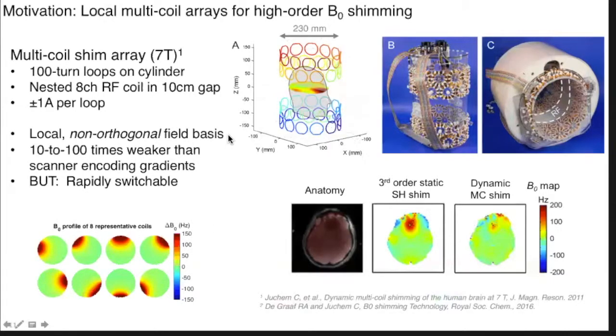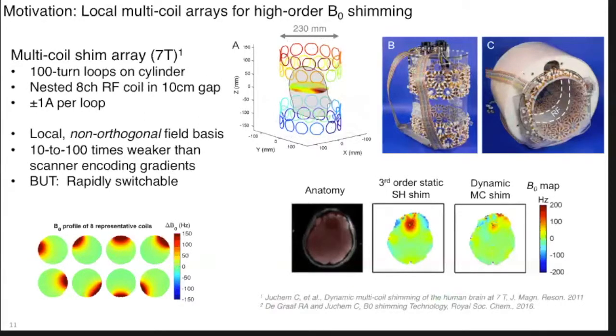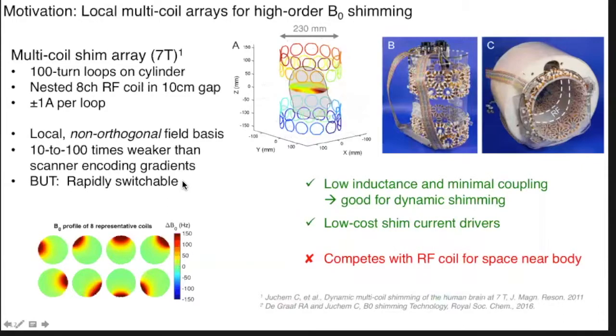So what I point out about this is that it's a non-orthogonal basis. That might seem bad at first, but it gives you a lot of flexibility for tailoring the field around the head. And it's 10 to 100 times weaker than the scanner's encoding gradients. These don't have to be strong fields. They just have to be spatially independent so that you can create high spatial frequency offsets. And very important is that these are little loops, so they're rapidly switchable. They don't have a lot of inductance. They don't create eddy currents. So this is great for what's called dynamic shimming, where you switch the shims very quickly.